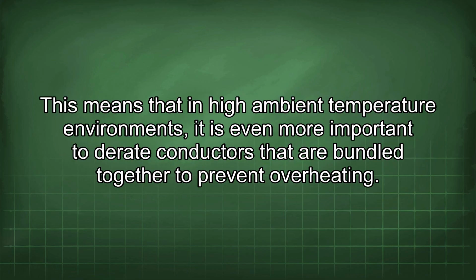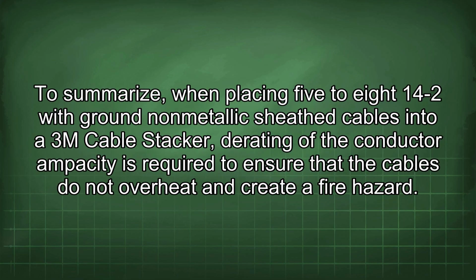This means that in high ambient temperature environments, it is even more important to derate conductors that are bundled together to prevent overheating. To summarize, when placing 5 to 8 14-2 with ground non-metallic sheathed cables into a 3M cable stacker, derating of the conductor ampacity is required to ensure that the cables do not overheat and create a fire hazard.